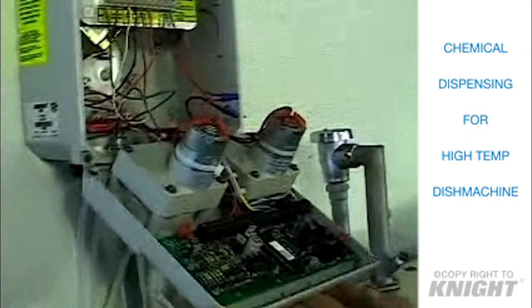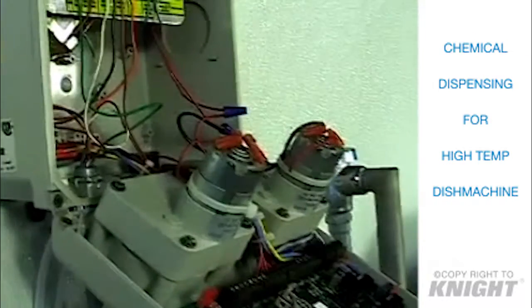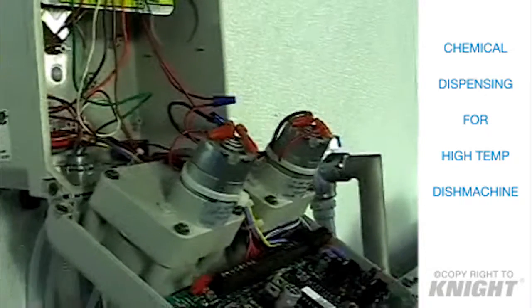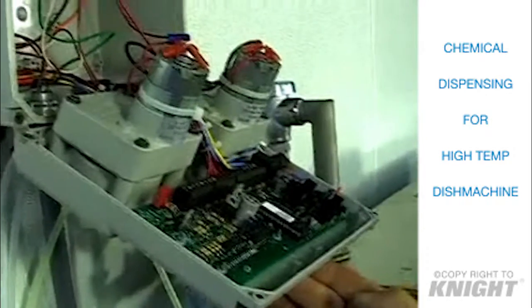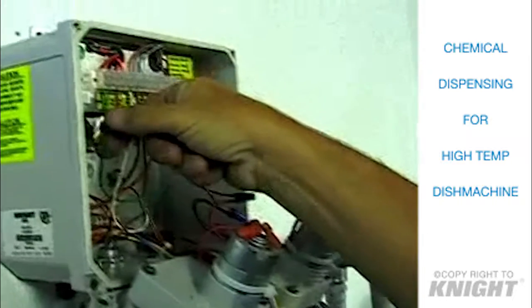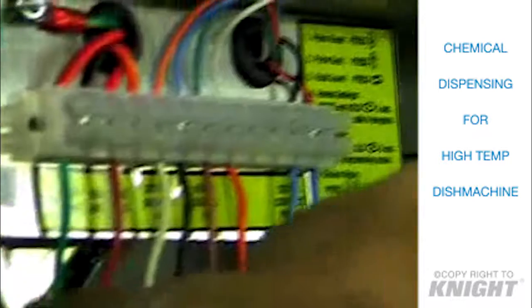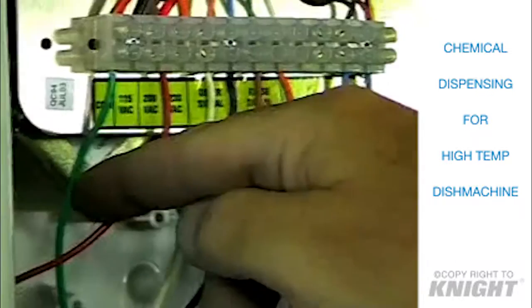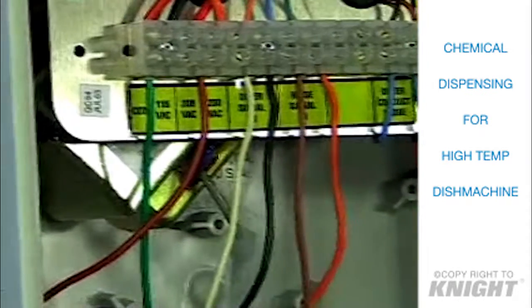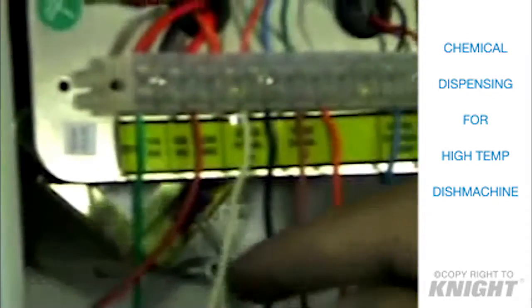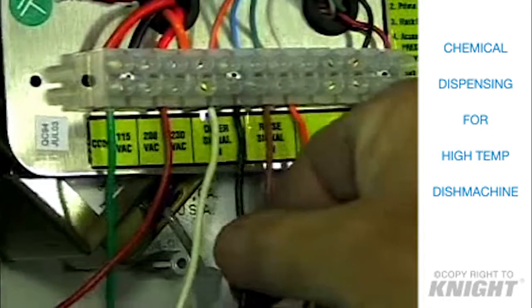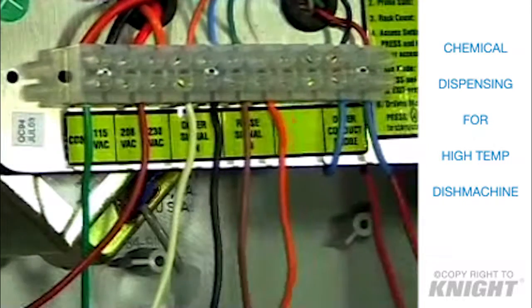You can see that the hookup is really quite similar to that of an AM14. It just works a little bit differently. So here is my incoming power, which is live all the time, coming from the line side of the contactor, the red and green wire that I showed you earlier. That's going to the line side of the contactor. My detergent signal is hooked up to the secondary side of the contactor, which is my black and white wire.